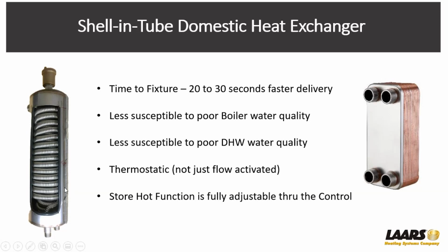Again, this vessel or the coils are surrounded by hydronic boiler water. So that's already hot water. And as soon as you turn on the faucet, especially on a 199, you have now a gallon of water to allow this boiler to now fire, go through its pre-purge, light off, and run smooth. So also, time to fixture, you can also talk about cold water sandwiching.